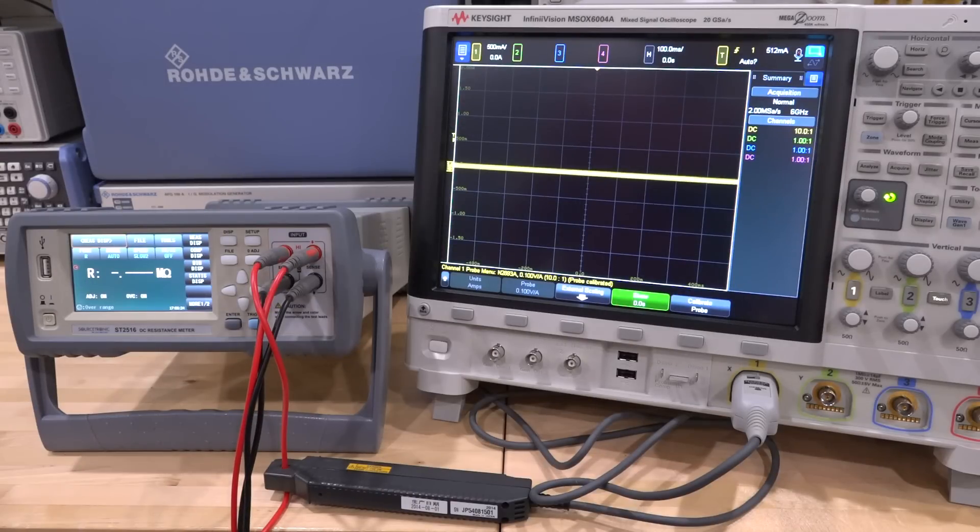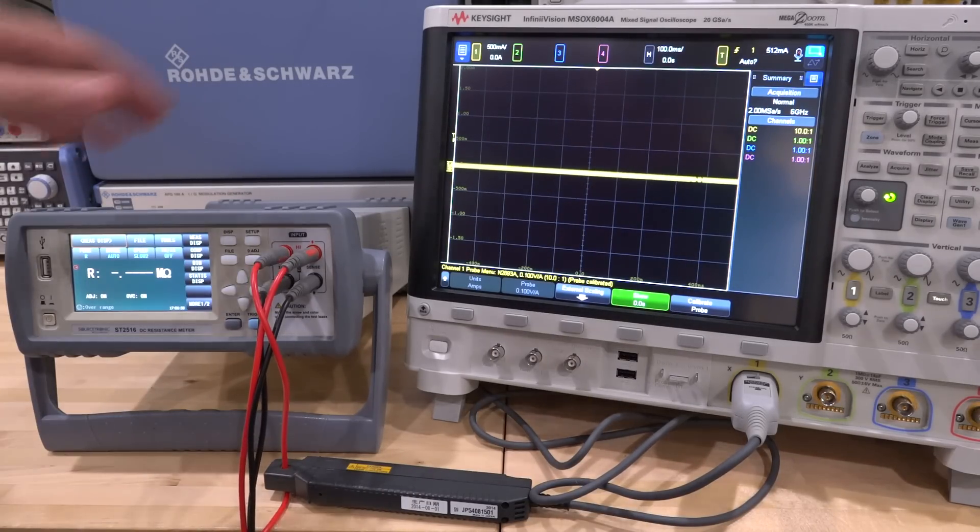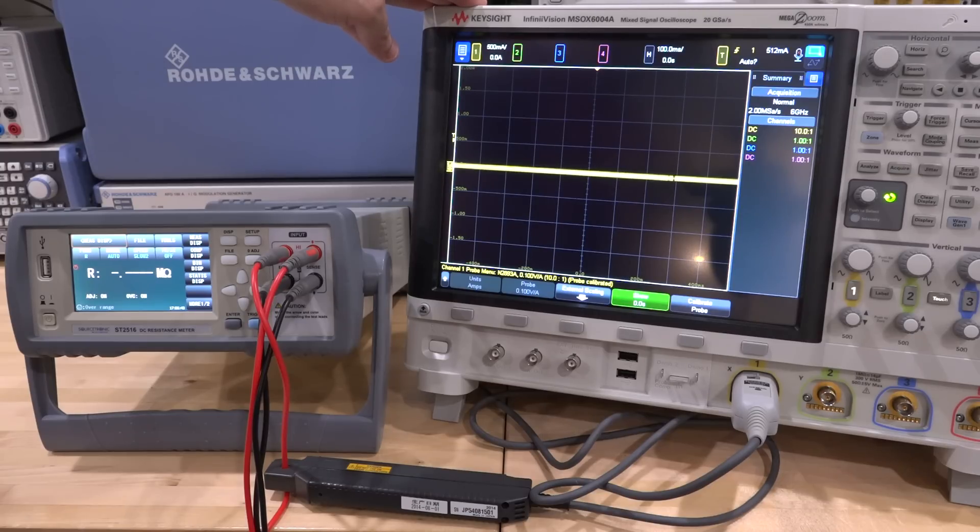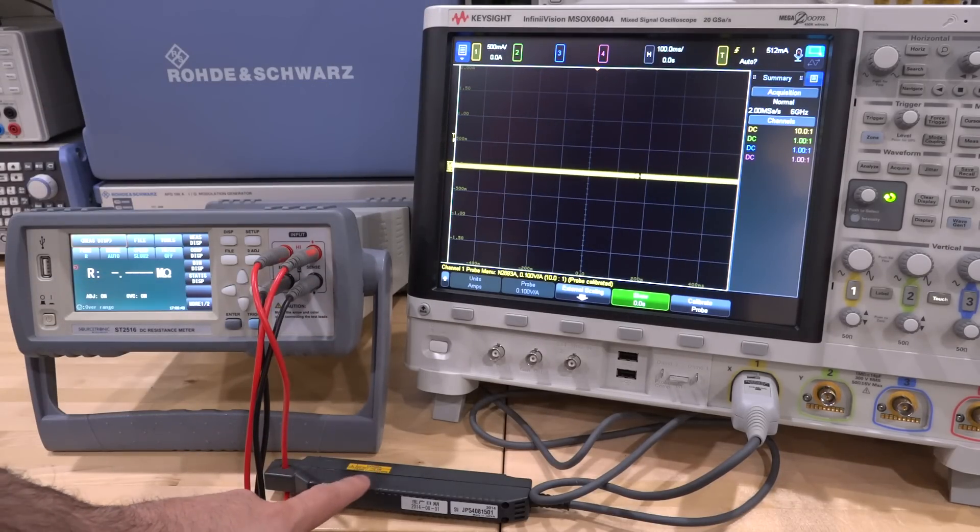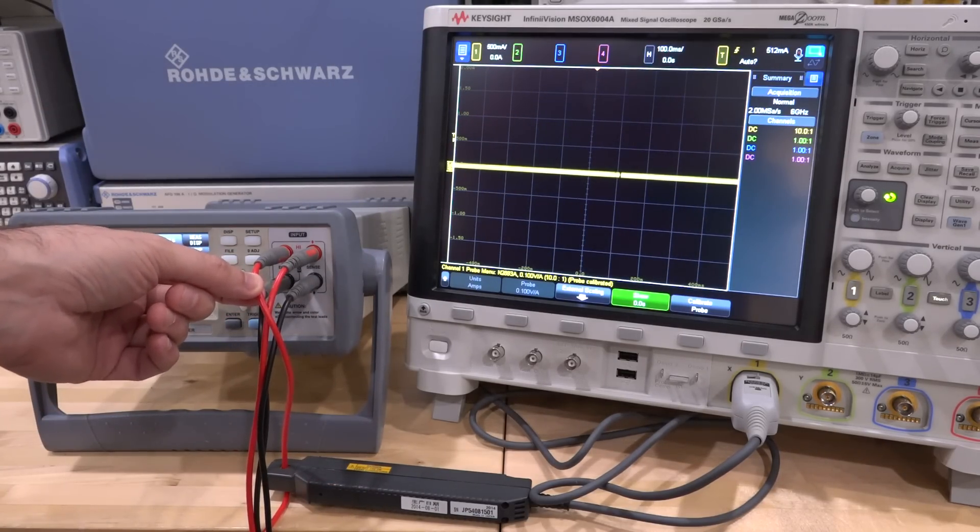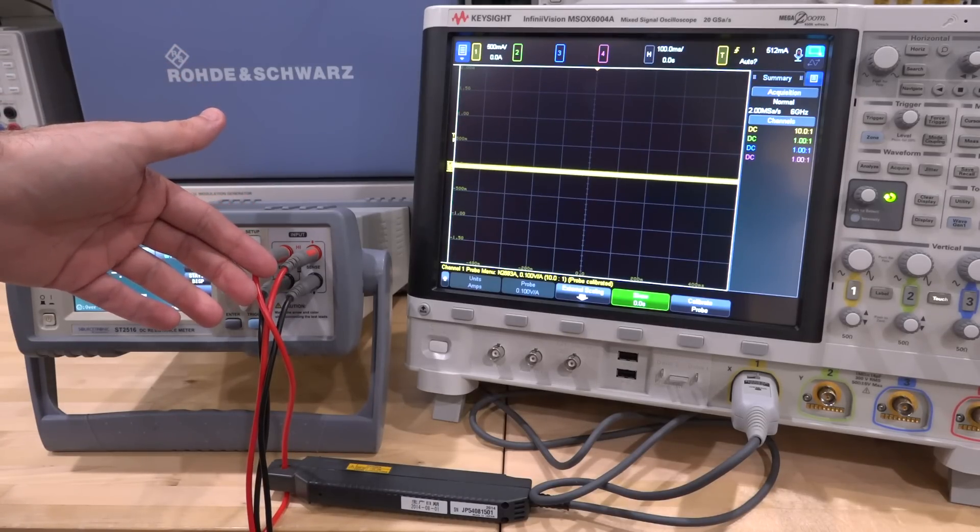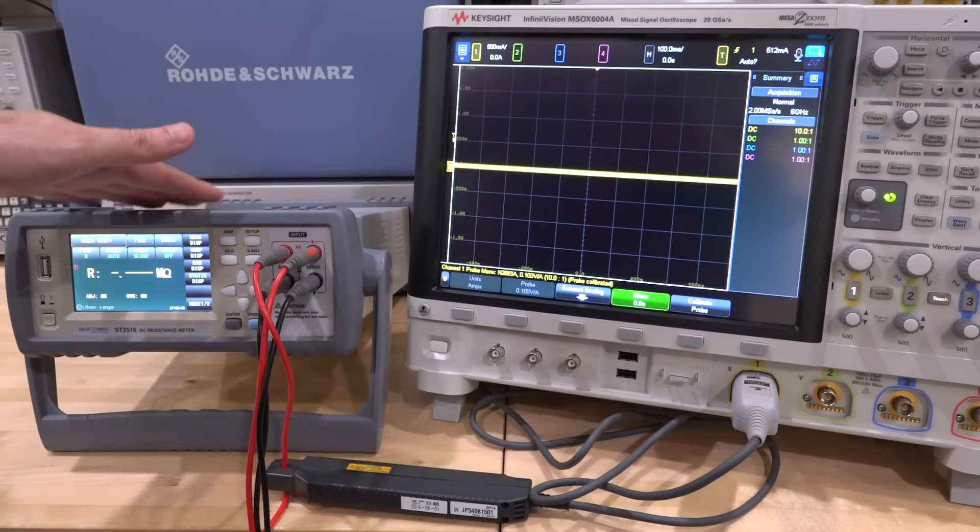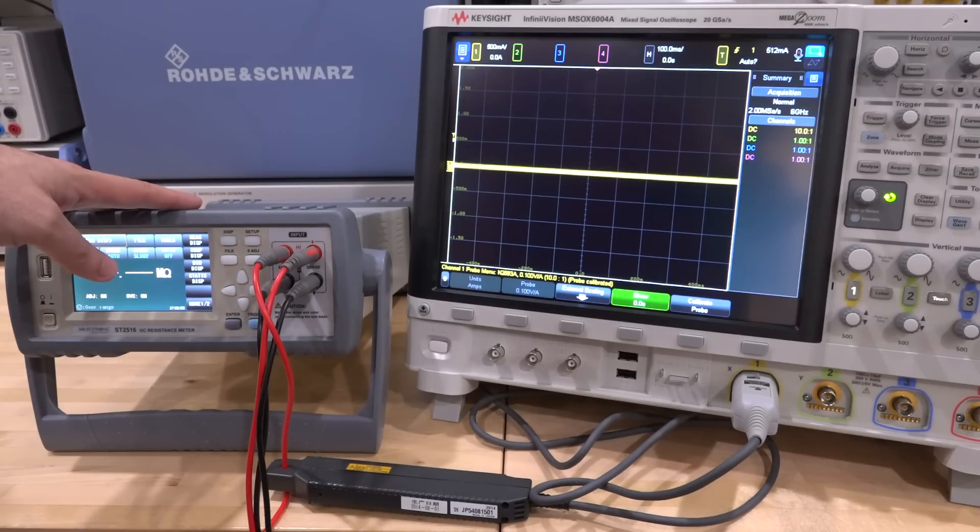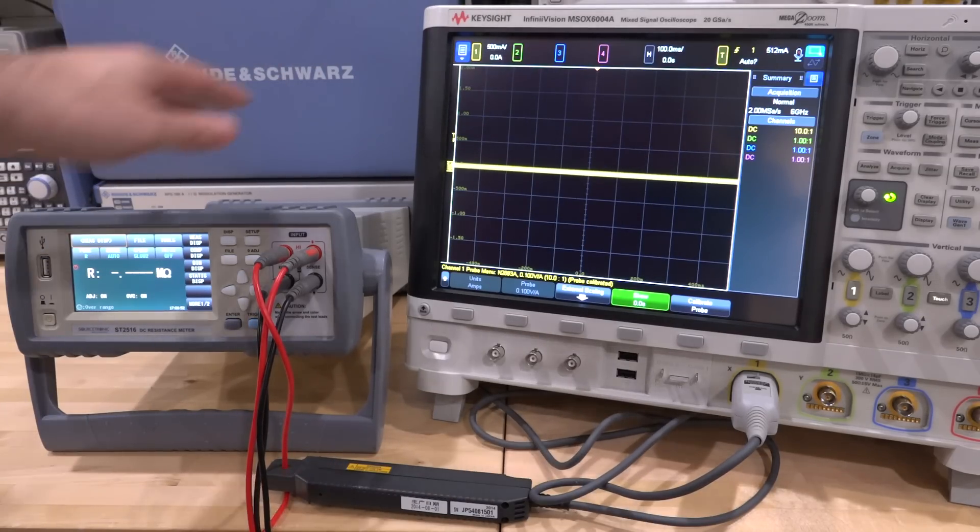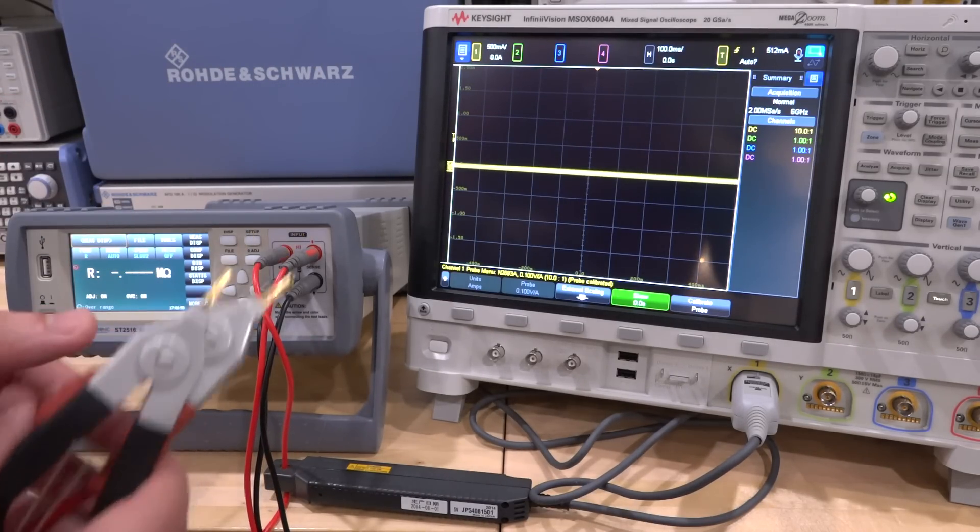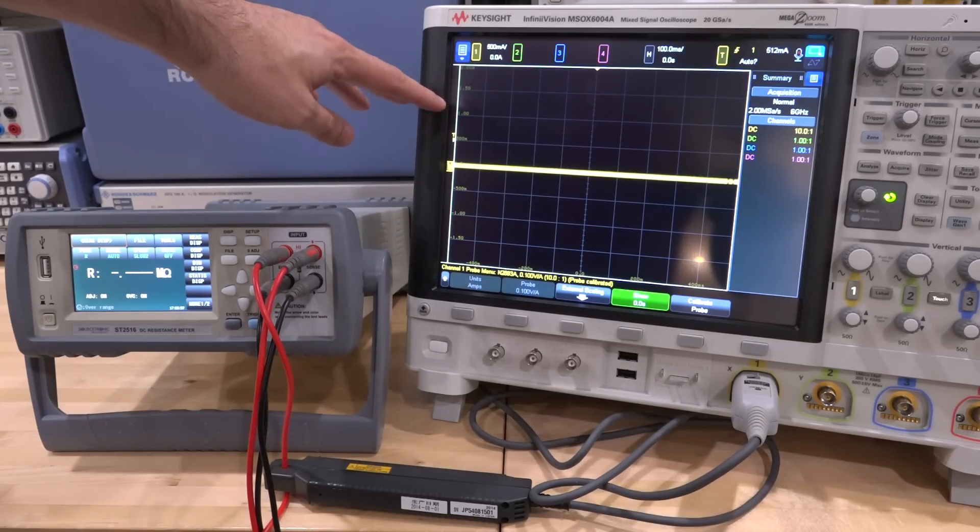Okay so here's our modified setup. Now all I've done is that I have added an oscilloscope in this case the Keysight MSOX 6004A and there is a current probe connected to it wrapped around the force terminal. So any current going through the force terminal that this instrument generates which goes through your device under test can be shown here in real time.